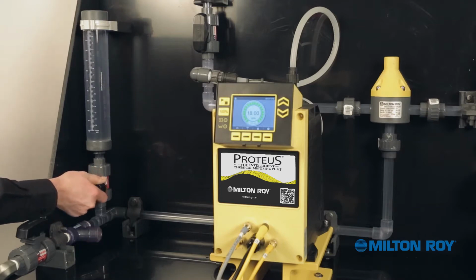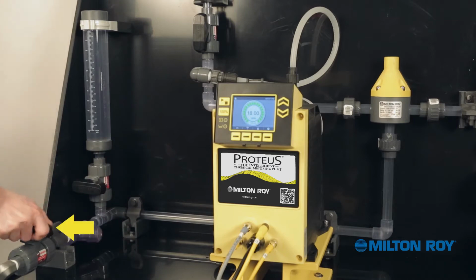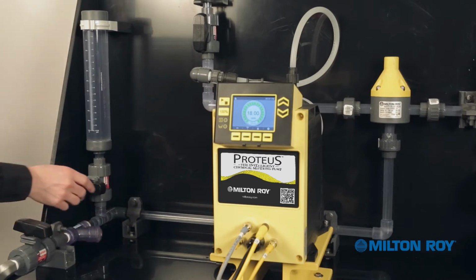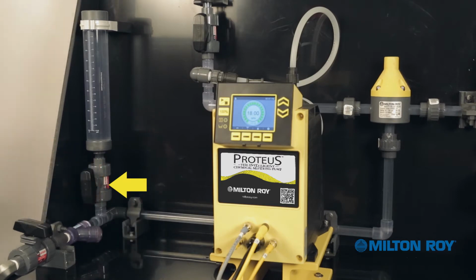Then take the pump out of service by closing the valve to the reservoir tank and open the valve to the calibration column. Be sure to make note of the starting fluid level.